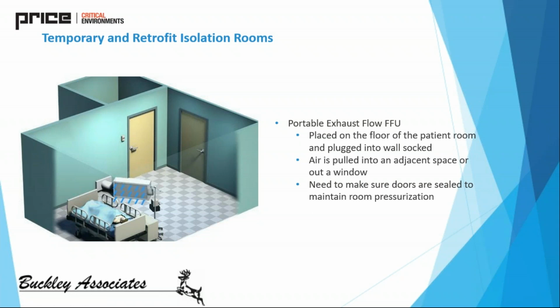An exhaust fan filter unit can also be placed on the floor of a patient's room. We have the ability to do this and then just duct it to an exterior room. Here we can see it's being ducted to the outside of a building. It's important again in this scenario that we seal all cracks in here to ensure proper filtration and negative isolation of this room. But nonetheless, this is another configuration that we are seeing quite a bit for these temporary facilities.